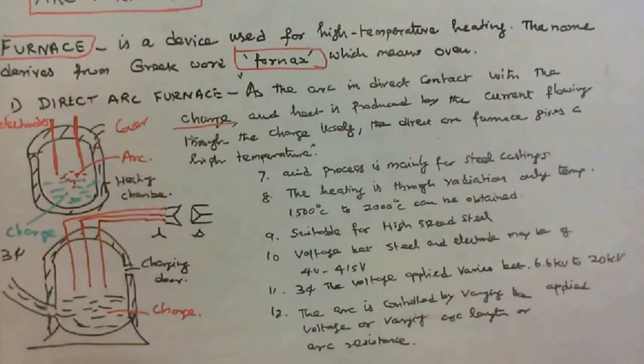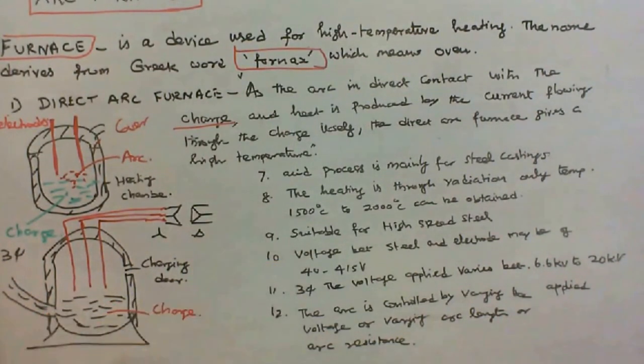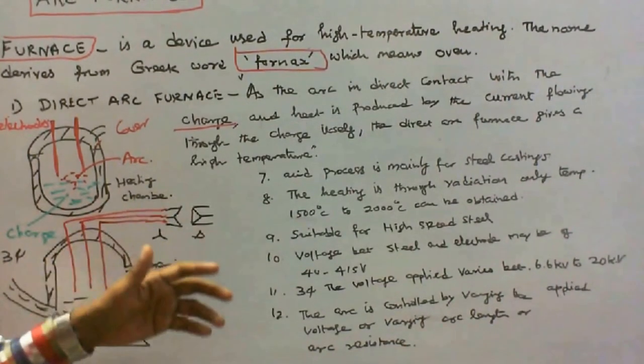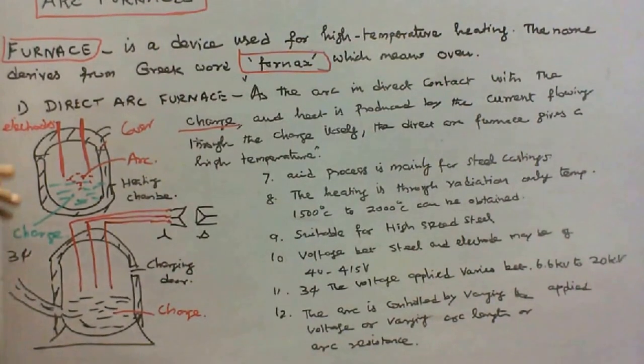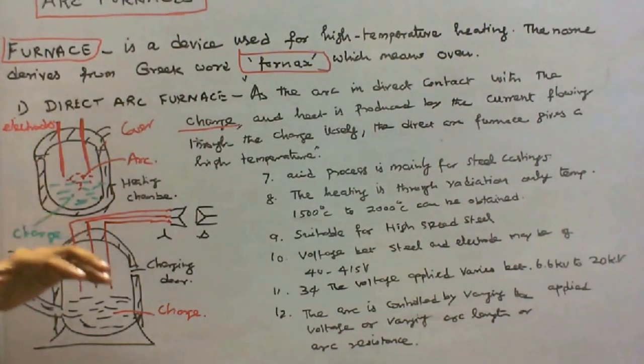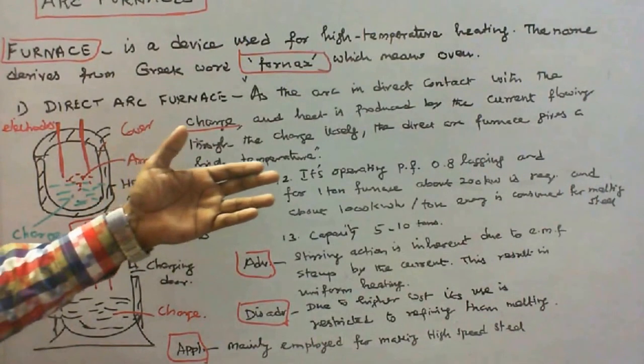Voltage between steel and electrode may be of 40 to 415 volts. In three phase, the voltage applied varies between 6.6 kV to 20 kV. The arc is controlled by varying the applied voltage, or by varying the arc length, or by varying the arc resistance. Its operating power factor is 0.8 lagging.